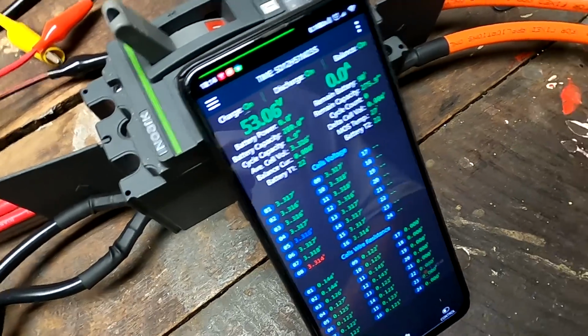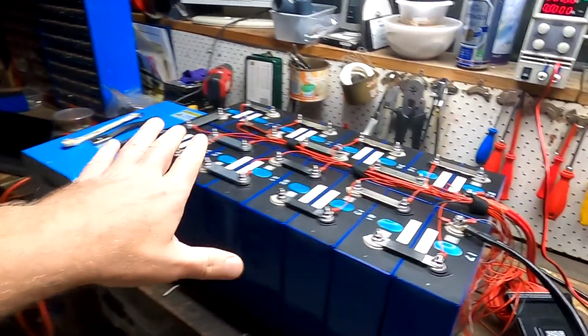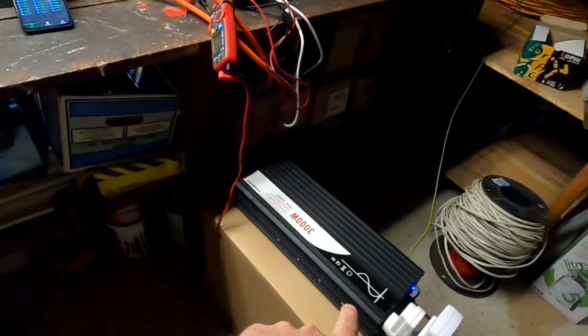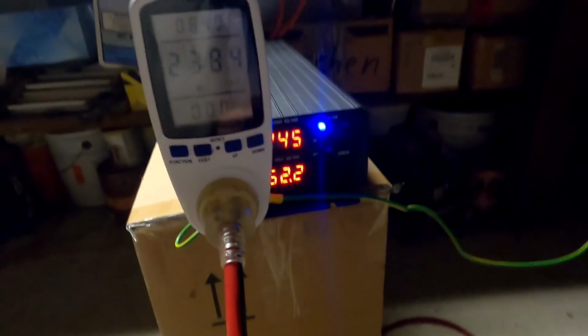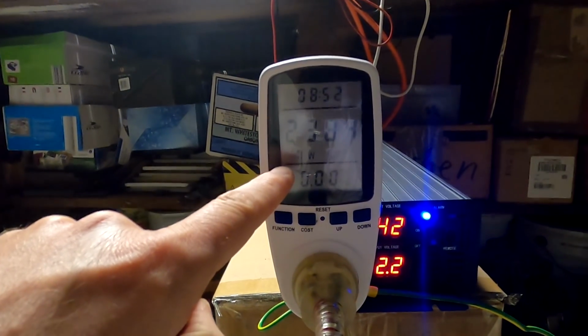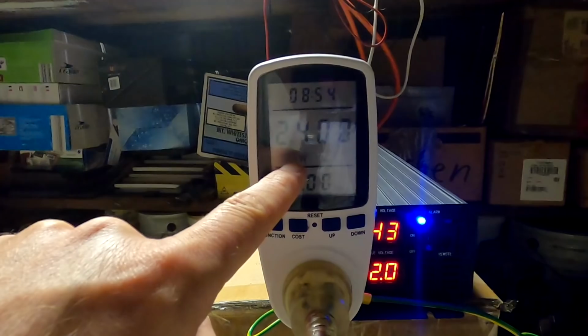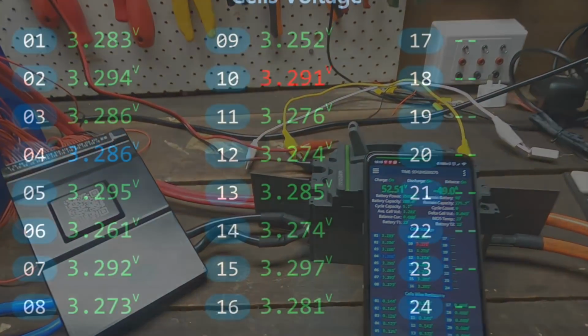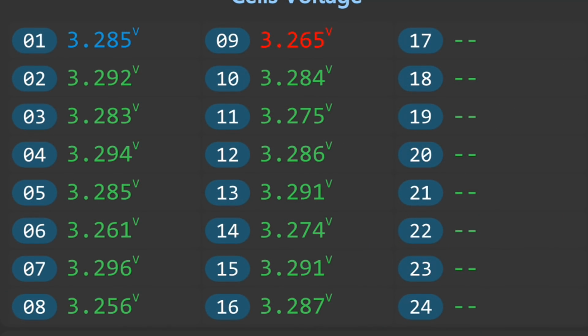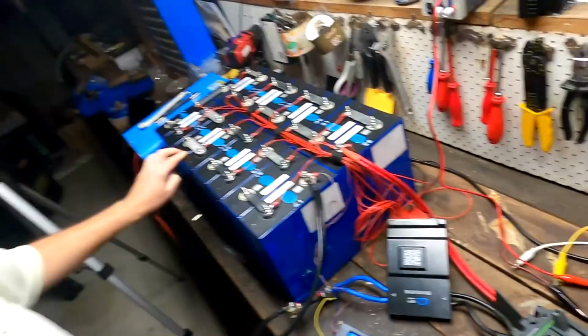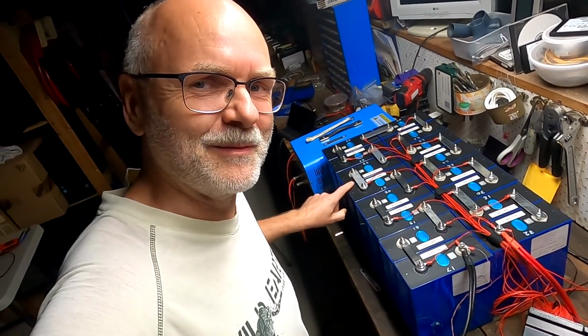I think the charger has a fault now because I've disconnected the battery and the inverter was on under voltage. Open the charge port again. Now that looks better. Yeah, because I disconnected the whole battery here, everything turned off basically, and the inverter had an under voltage situation then. 2.3 kilowatts, 2.4 kilowatts we are pulling, and there cell number 6 is fixed. Nice. Thanks to Paul's super aluminium bus bars.